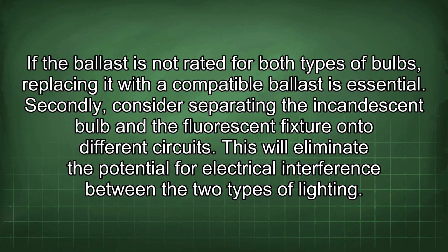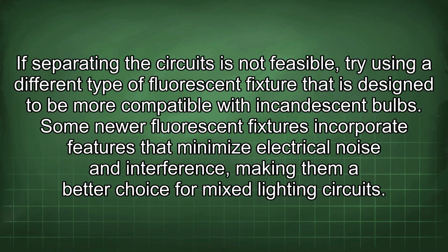Secondly, consider separating the incandescent bulb and the fluorescent fixture onto different circuits. This will eliminate the potential for electrical interference between the two types of lighting. If separating the circuits is not feasible, try using a different type of fluorescent fixture that is designed to be more compatible with incandescent bulbs.